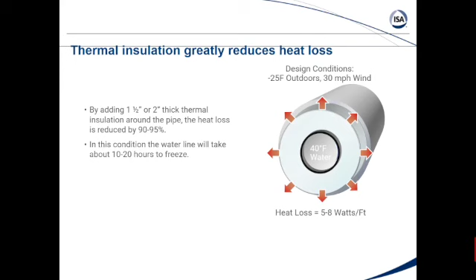As you can see here, just same situation, minus 25, 30 mile an hour wind, 3-inch diameter pipe. We took no insulation, 100 watts per foot heat loss. Now we're down to 5 to 8 watts per foot. And that is a much more manageable amount to put heat back into. So that's what we do. This diagram here shows you a little bit about what I was mentioning, in that a non-heat trace pipe, that fluid will slowly get down to the temperature you don't want it to be. When you have a heat tracer on that pipe, all we're doing is trying to keep that temperature the same, not really ramp it up.